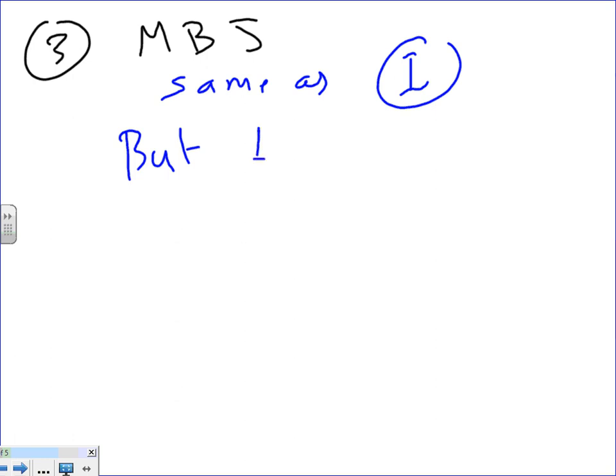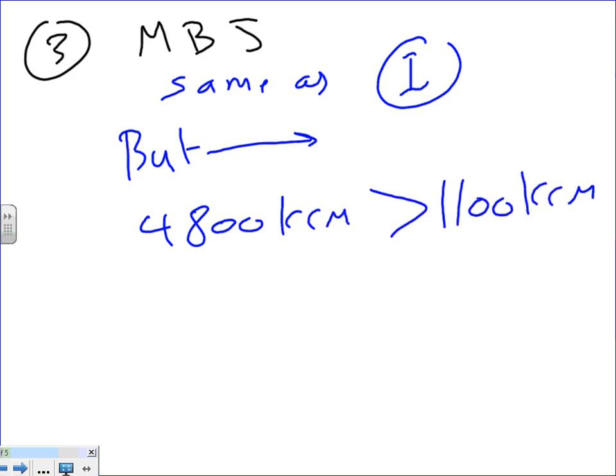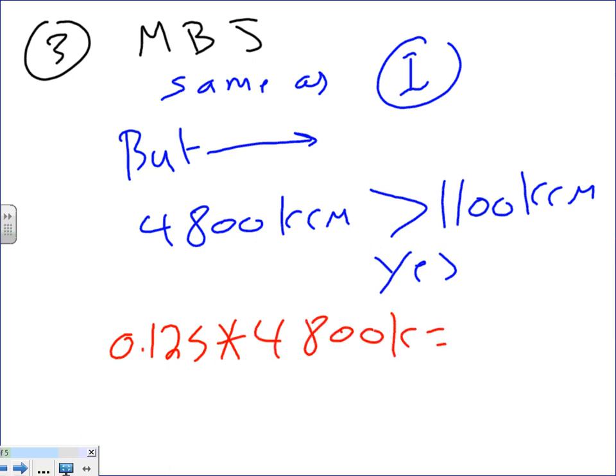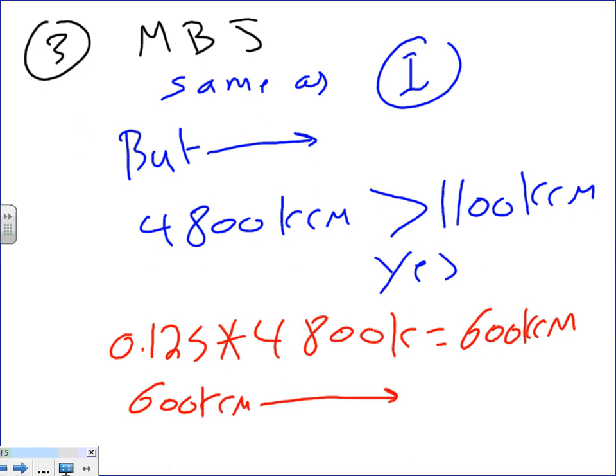If what we end up with is 4800 kcmil, is this more than 1100 kcmil? The answer is yes. Then this is where you use the 12.5%, 0.125 times 4800K. Don't forget the K. Same as one, except if it's higher than 1100 kcmil, you have to do a different calculation, and that gets me 600 kcmil. Is that even a 600 kcmil size? Yes, it is. If it's not, you take the 600 kcmil. If you came up with something different, take it to Chapter 9, Table 8, and that will get you 600 kcmil.